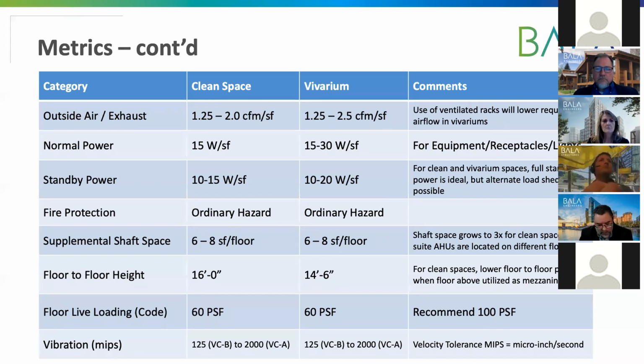And this is really predicated on the fact that with a clean room space, as I mentioned, we have the 1 to 2 CFM per square foot of outside air, but clean rooms need to maintain about 20 air changes to maintain their classification. And that's 20 air changes of recirculating air. So we're roughly running 3 CFM per square foot total, and we blend in the outside air. But that 3 CFM per square foot represents a large volume of space needed to accommodate that ductwork.